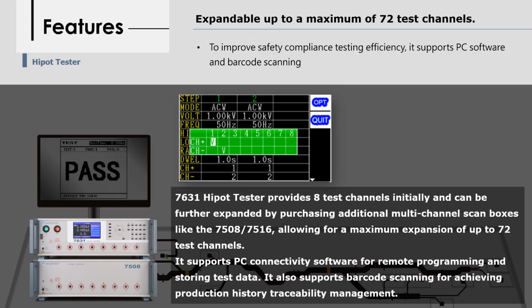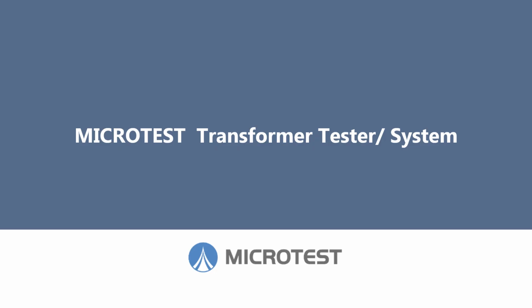Testing the safety compliance of a production line can be time-consuming. To enhance production efficiency, the Microtest Hipot Tester offers a multi-channel measurement solution. When paired with the 7631 Hipot Tester and a multi-channel scanning box, it can span up to 72 sets of test channels. This system also supports PC connection. Now, let's explore the transformer testing instrument, a comprehensive product for transformer testing.